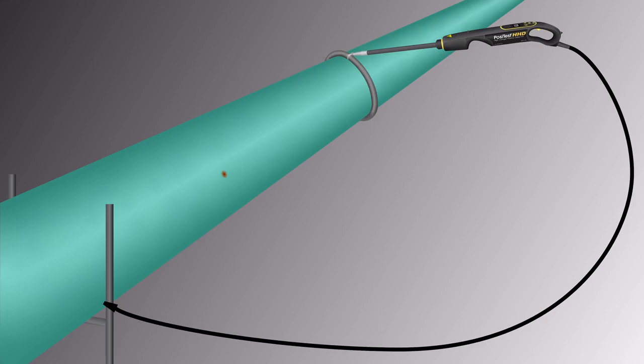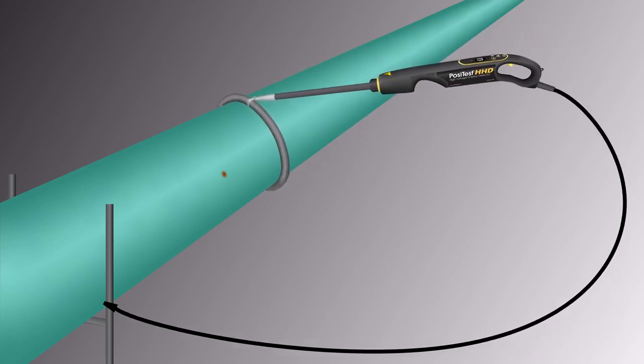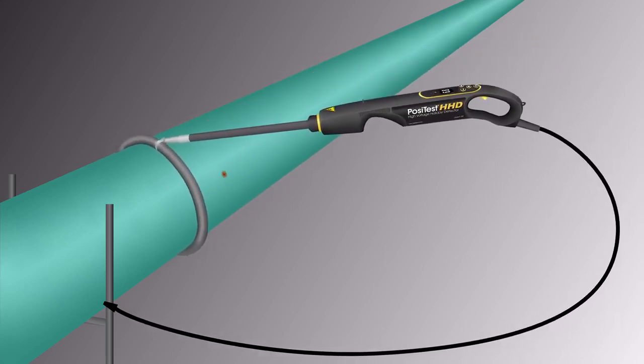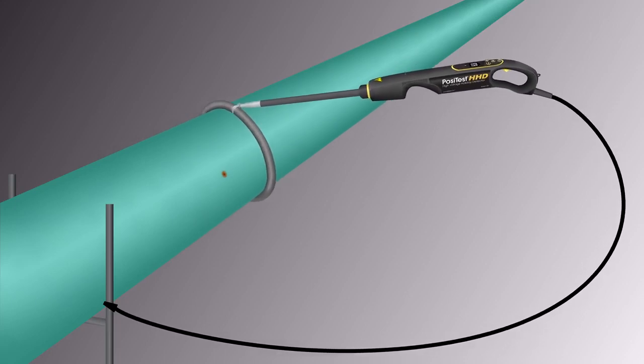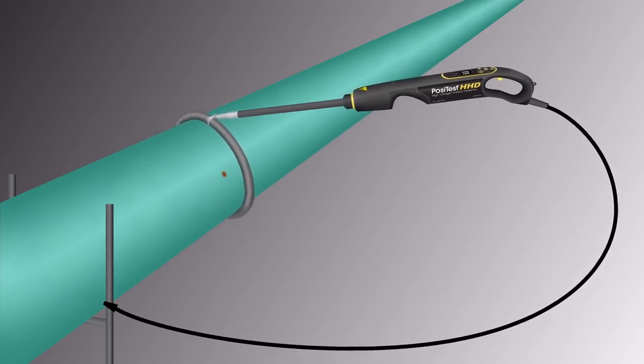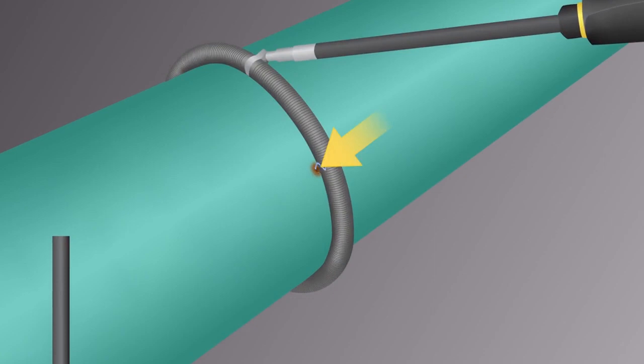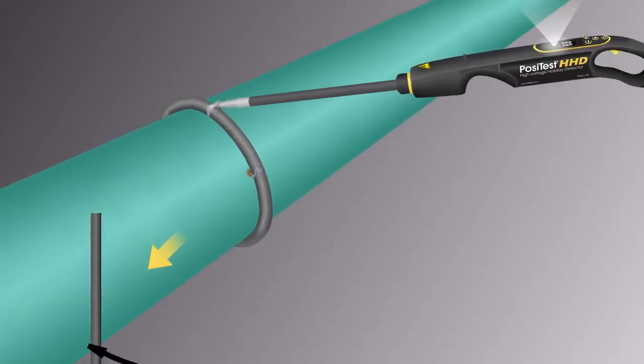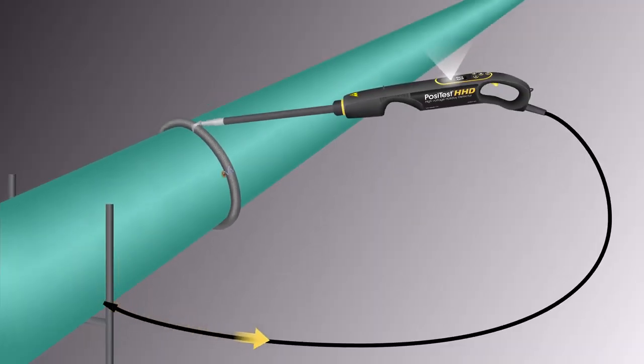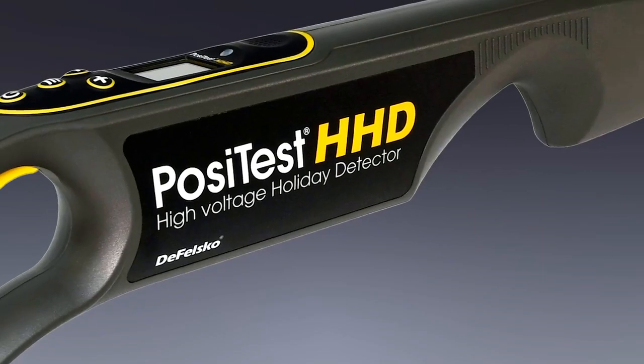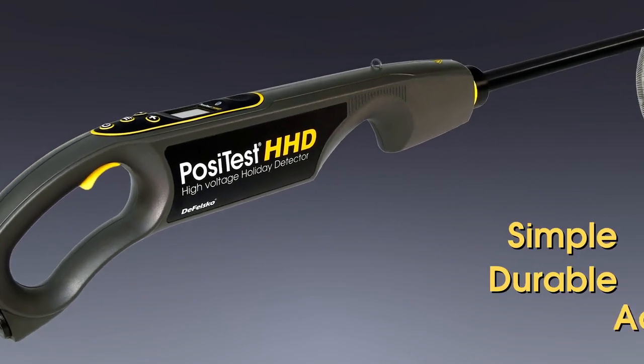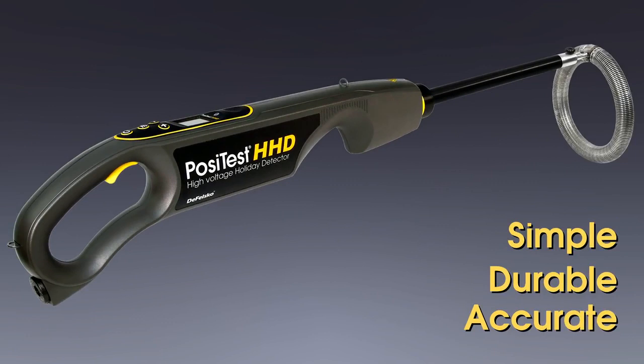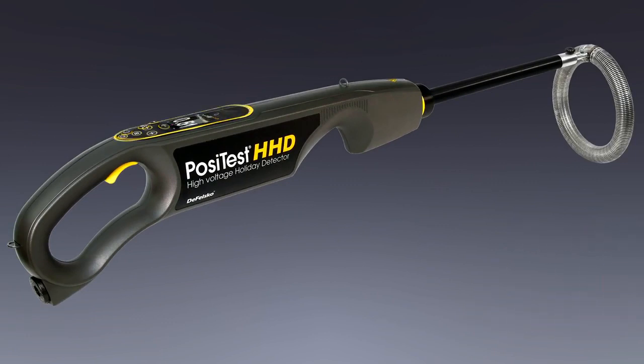The principle of operation for high-voltage holiday detectors is similar to low-voltage detectors. The charged electrode is passed over the coating, and when a holiday is encountered, current flows from the electrode into the substrate below. The current returns to the detector through the ground wire, completing the circuit and triggering audible and visible alarms. The Positest HHD High Voltage Holiday Detector is the simple, durable, and accurate way to find defects, pinholes, and holidays in the coating system.